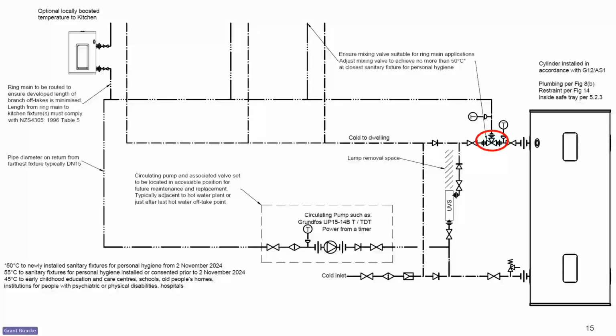Not every off-the-shelf tempering valve will work. So you must make sure you've got a tempering valve that the installation instructions show tempering, mixing water down to a lower temperature in a whole ring main. Once we've commissioned the system, we want to adjust the temperature on that ring main so that the hot water coming out of the nearest sanitary fixture is no more than the allowable temperature, depending on when the fixture was installed. So it's important that we can get reasonable access to those valves also.